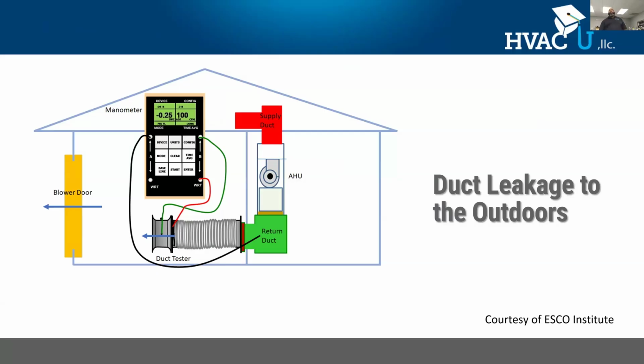All right, we have our blower door operating and our duct leakage tester operating. The way this works, whatever the blower door's direction of airflow, either pressurized or depressurized, I have to have the duct leakage tester pushing the same way. When I do that, I'm trying to get the pressures to cancel out. When they cancel out, the house and the ducts are at the same pressure, so they can't leak to each other. Then my only leakage that can occur is outside the building shell. And we're able to quantify that and put numbers behind it to see what our energy penalty is.